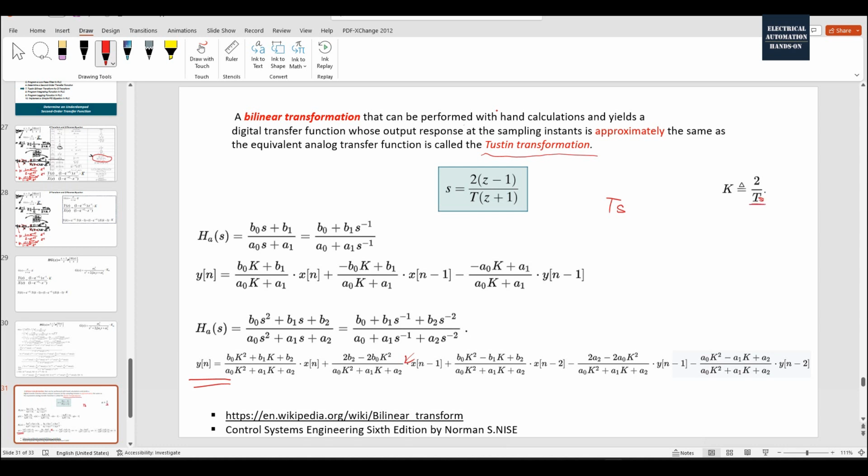this is the sample time, okay? Your sample time will be much less than 1 second. So if your sample time is higher than this, all those parameter approximations won't be accurate enough. Typically, I would recommend while using the computer or embedded system or PLC to implement this transform, your Ts will be much less than 200 milliseconds. Typically, I will use 100 milliseconds. That means 0.1 seconds.